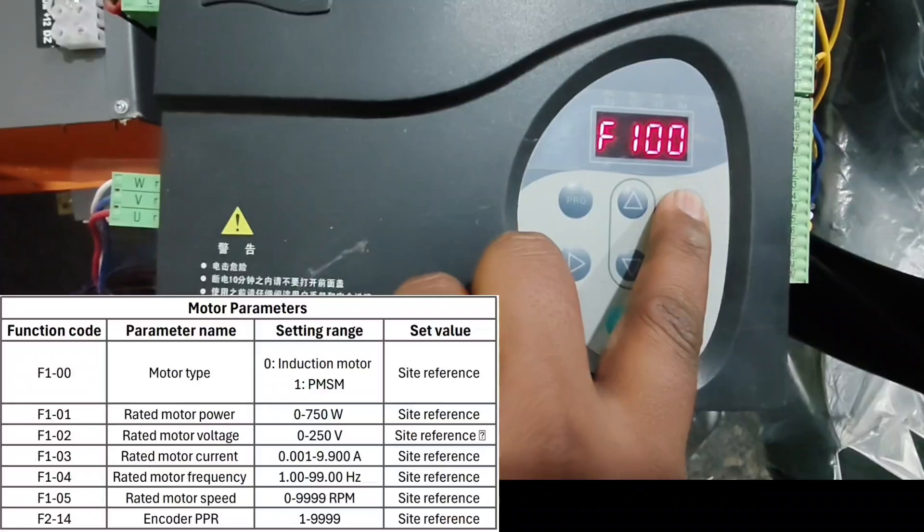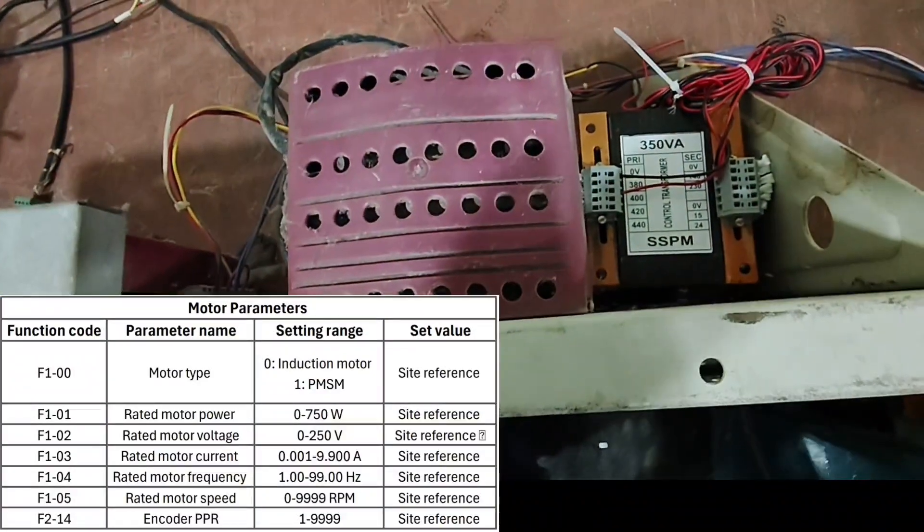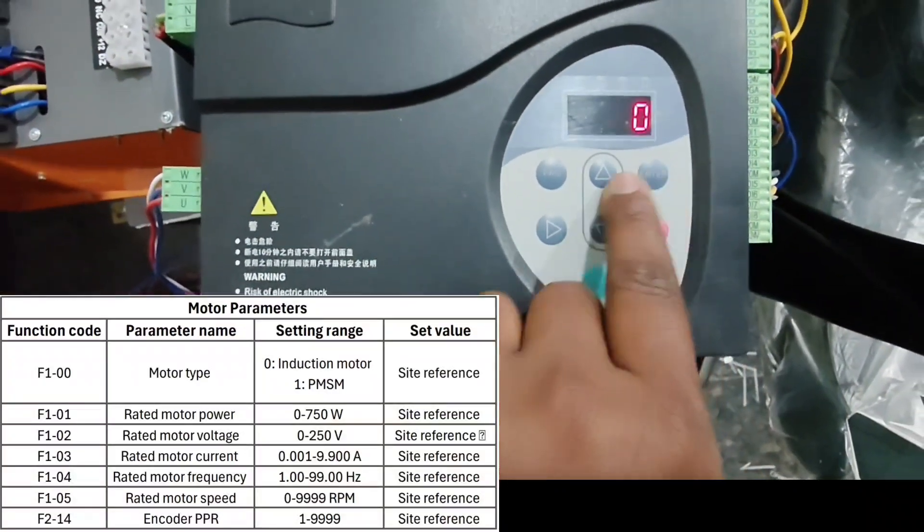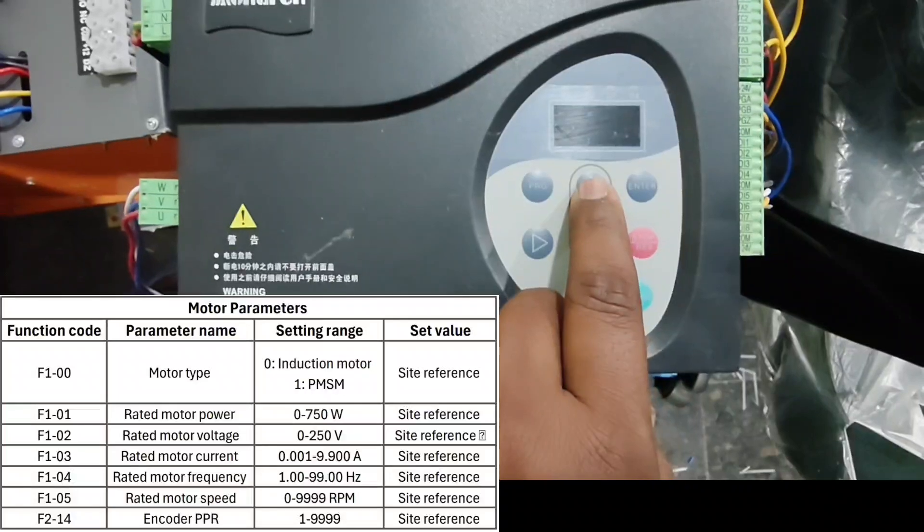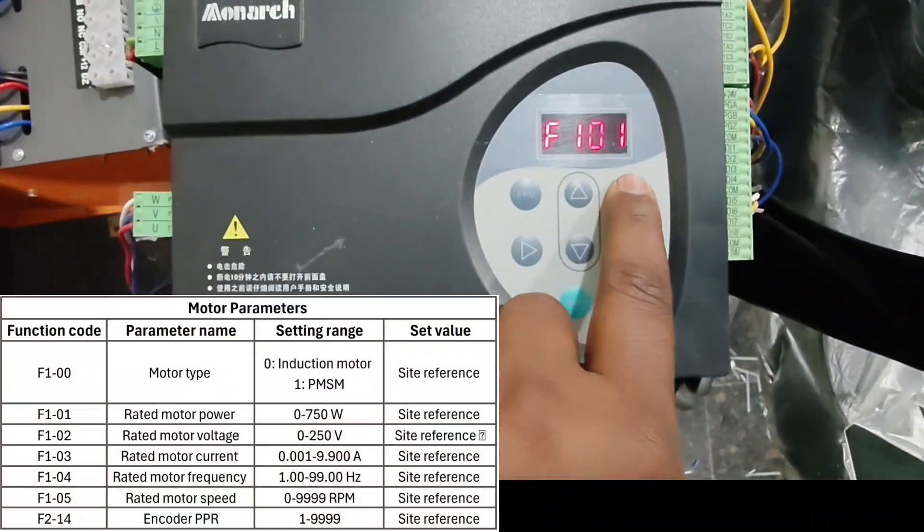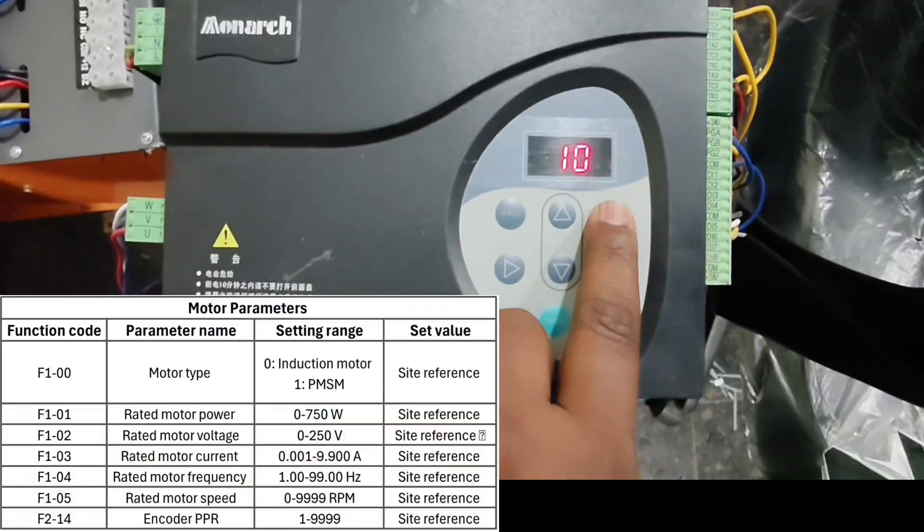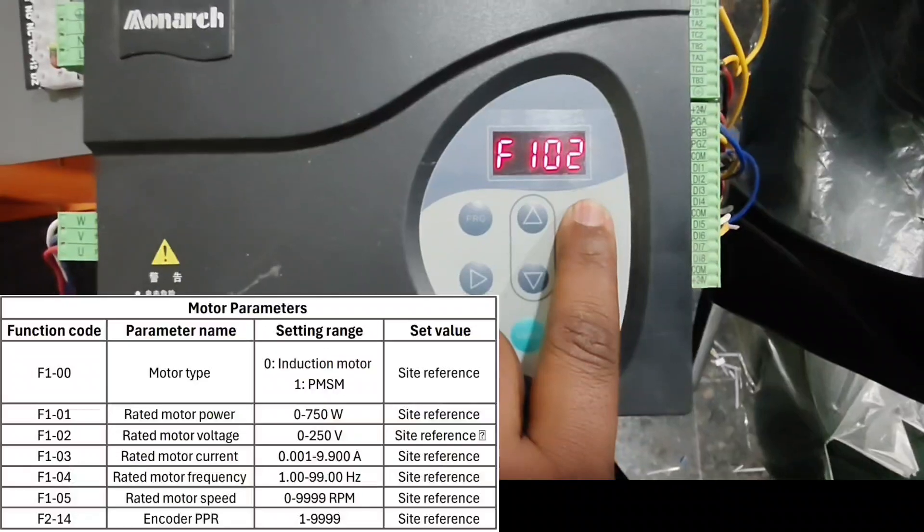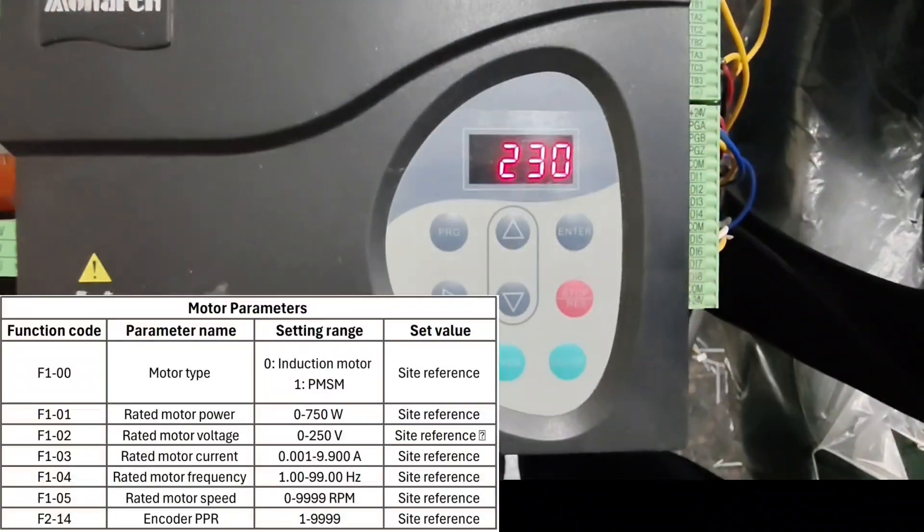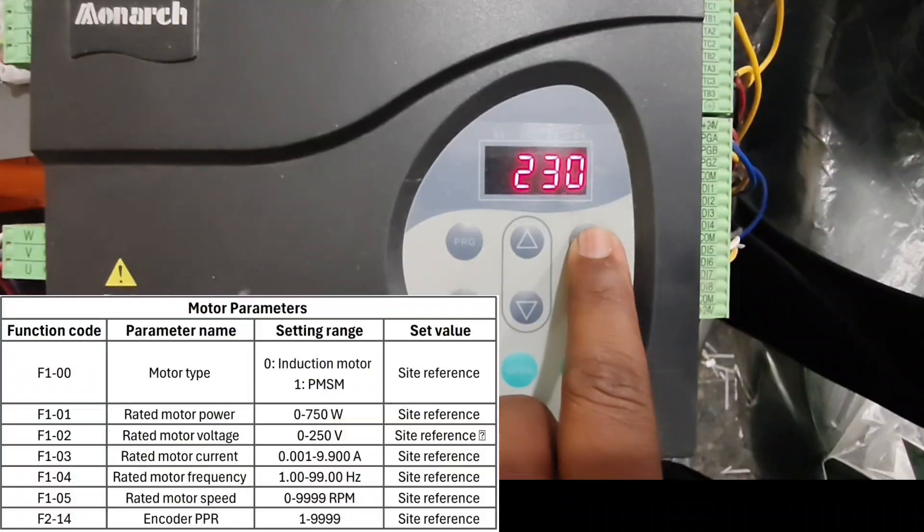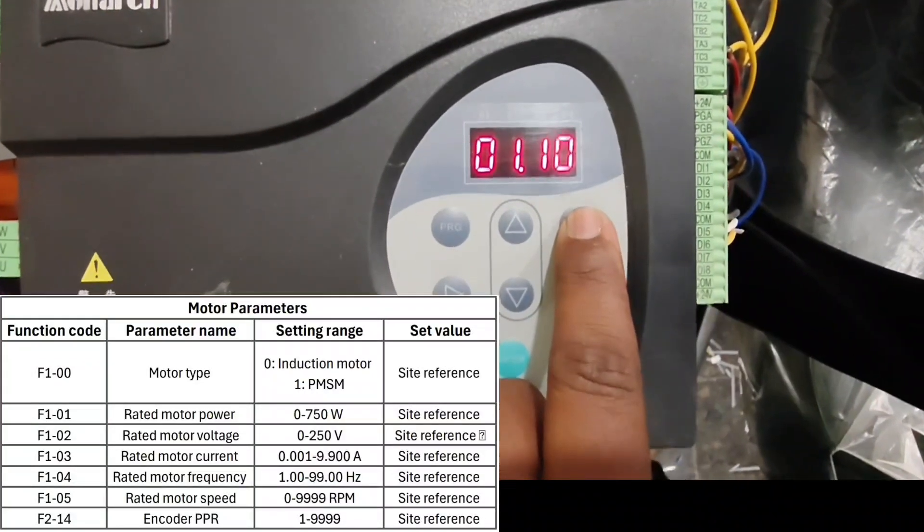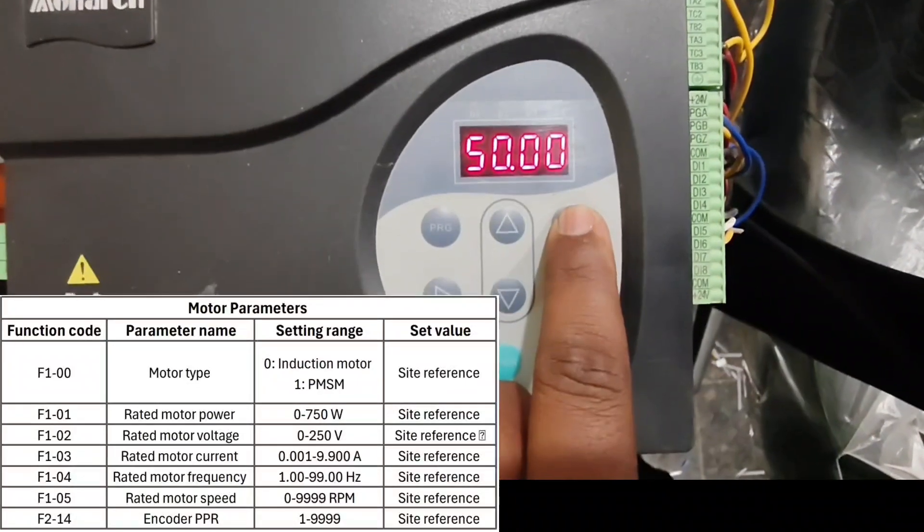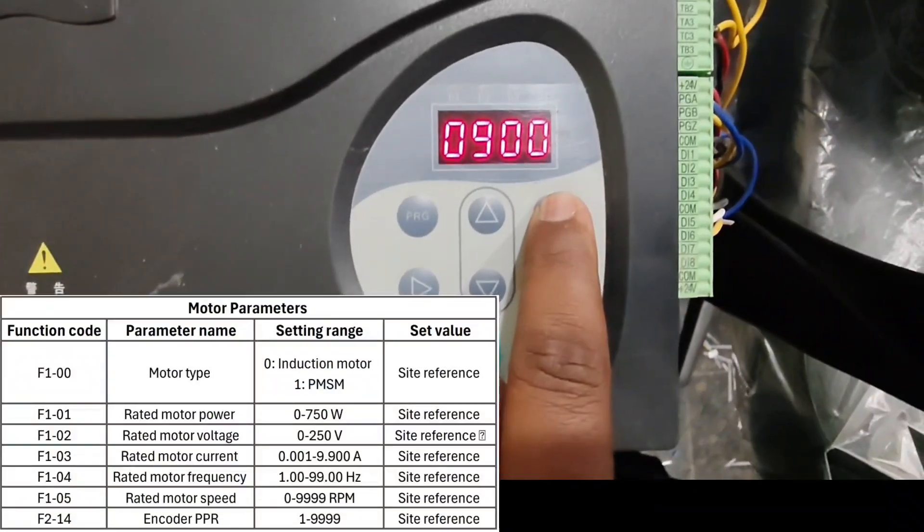F100 is motor type. This is an induction motor, set to 0. If the motor is a PM motor, set to 1. F101 is motor power, set to 100 watts. F102 motor voltage 230 volts. F103 motor amps 1.10. F104 motor frequency 50 hertz. F105 motor rpm 900.